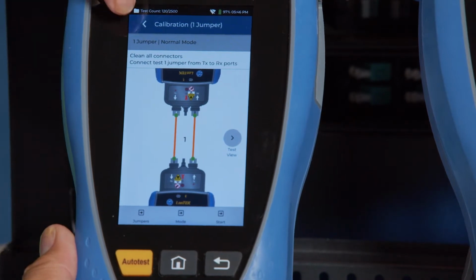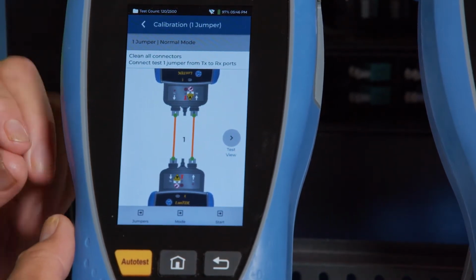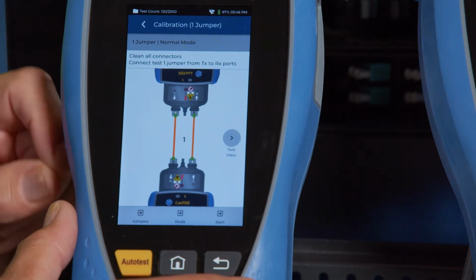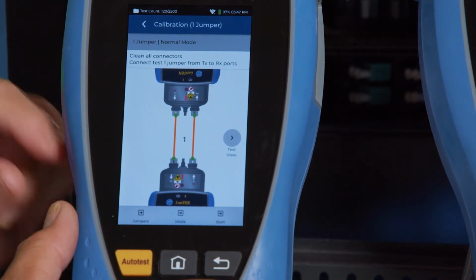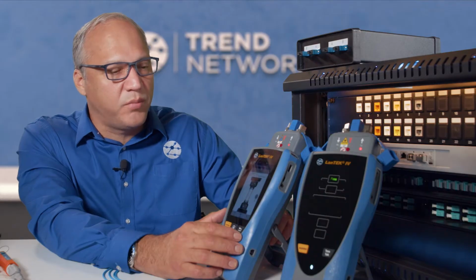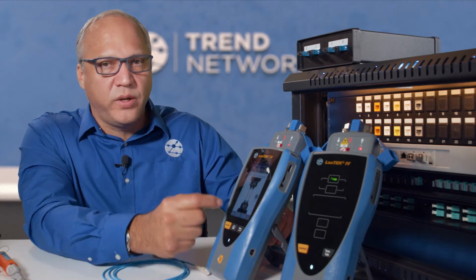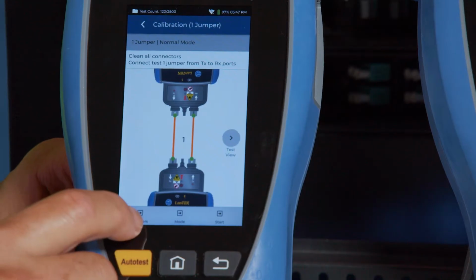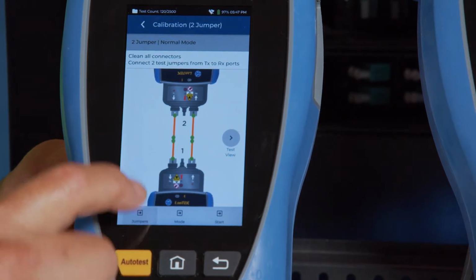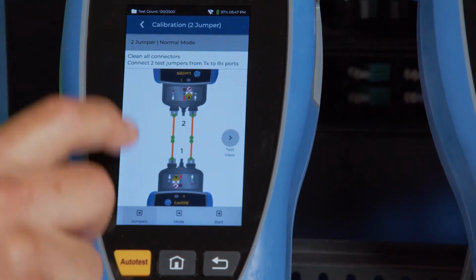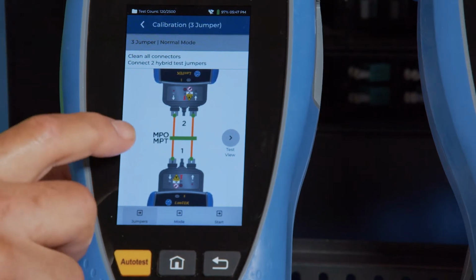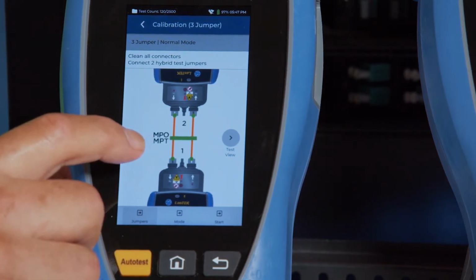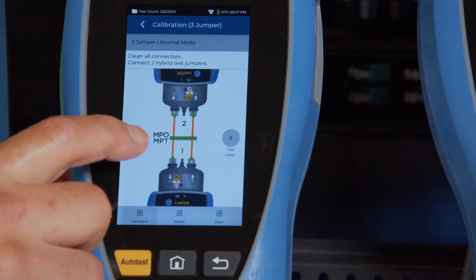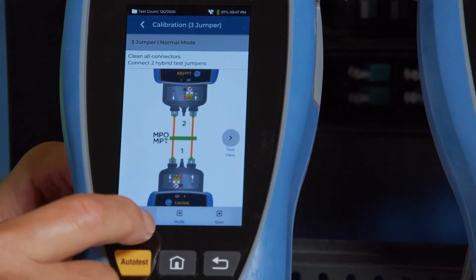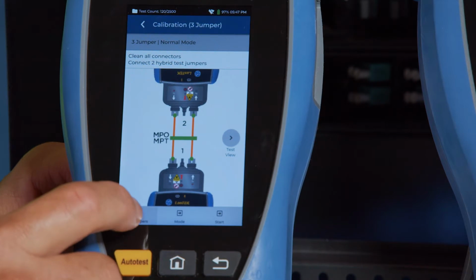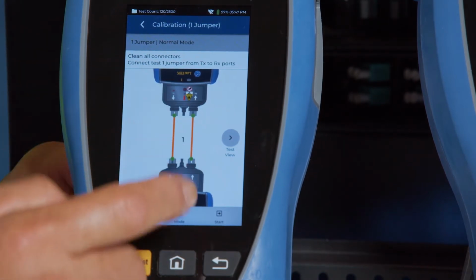So the first thing to look at is at the top, it tells us what the current setting is for the number of jumpers and the type of reference. So it's starting with one jumper normal. To cycle between 1, 2, and 3 jumper, we push the soft key down here at the bottom left, and it shows 2 jumpers, and it shows that at the top. 3 jumpers. Now with 3 jumper, we get a little different indication. It's showing an MPO and an MPT connection here, because that's usually when we perform a 3 jumper reference. And then back to 1 jumper.